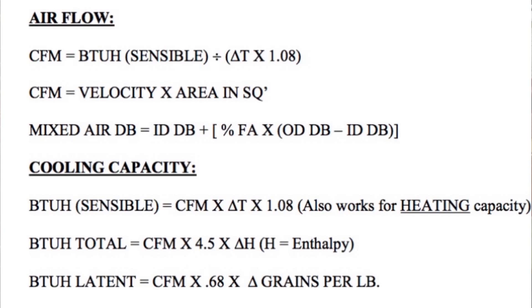Let's try another one. BTU equals CFM times delta T — your dry bulb temperature change — times 1.08. Let's try 1700 CFM with a delta T of 40, times 1.08. That's 73,440 BTU. With all that it only equals about 73,000, yet there are furnaces out there rated at 115,000 or 120,000 BTU residentially.